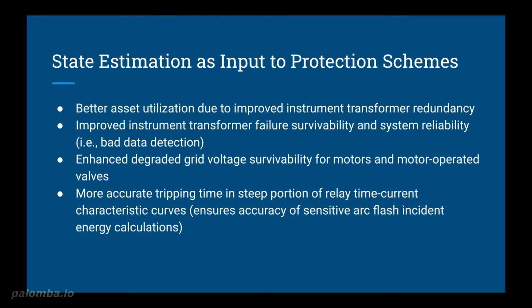Additionally, these devices pose a significant threat during degraded grid voltage conditions. Required motors are required to survive degraded grid voltage events in order to keep nuclear plants in a safe condition. This means that all safety-related loads required for postulated design basis accidents must retain the ability to auto transfer to the on-site emergency power supply if the degraded voltage relay monitored buses experience degraded voltage levels sufficient to require separation from the off-site circuit.